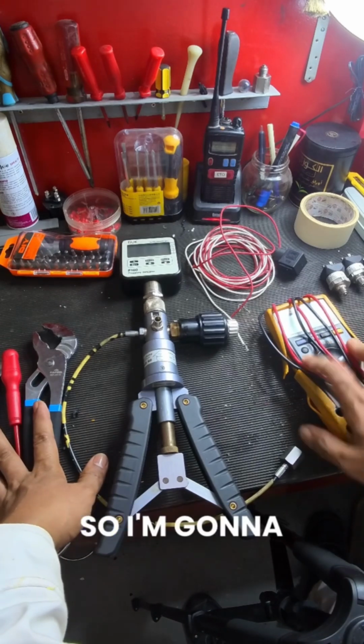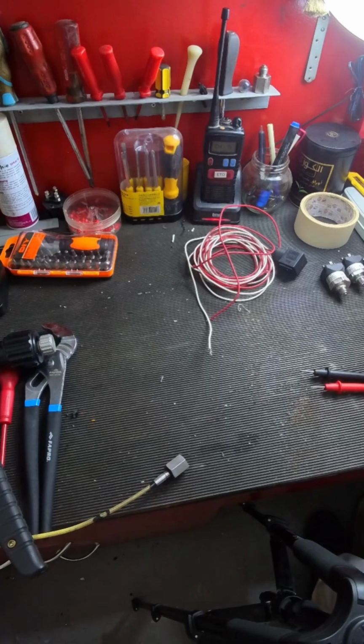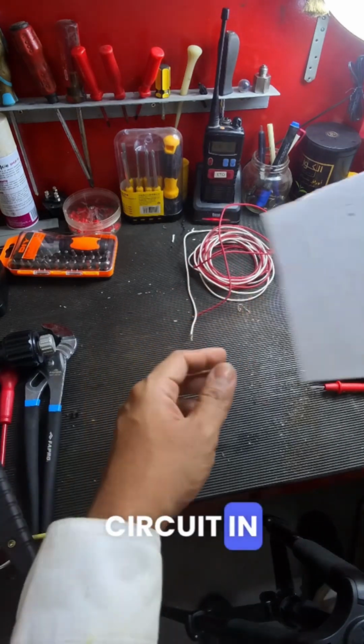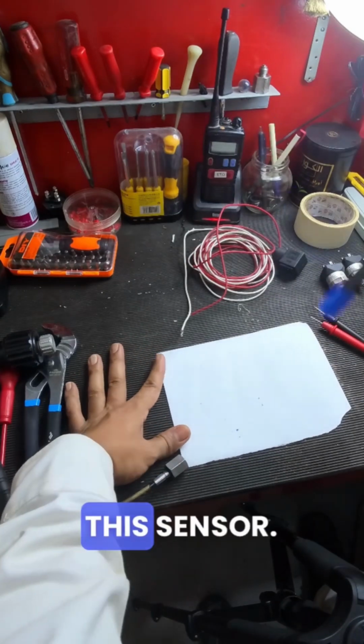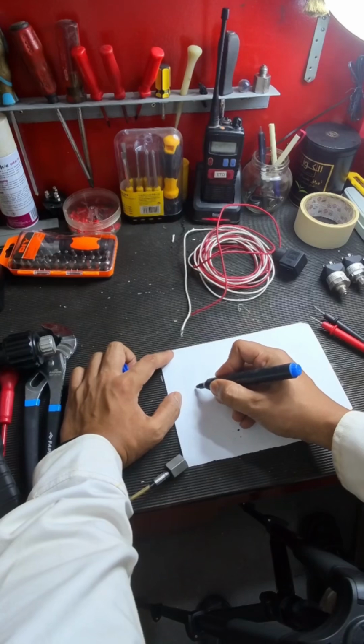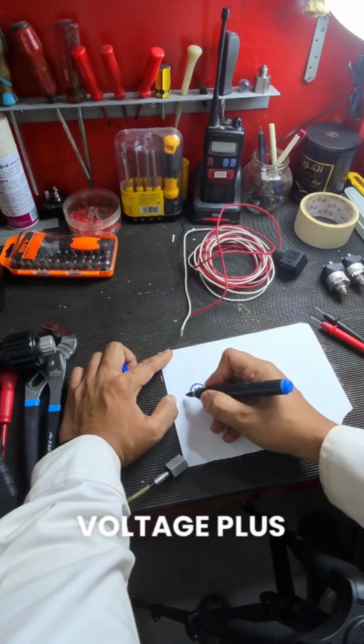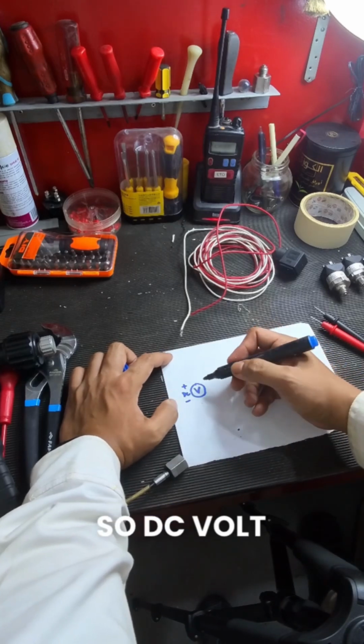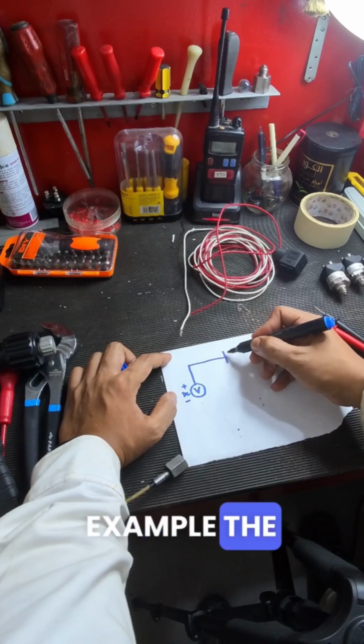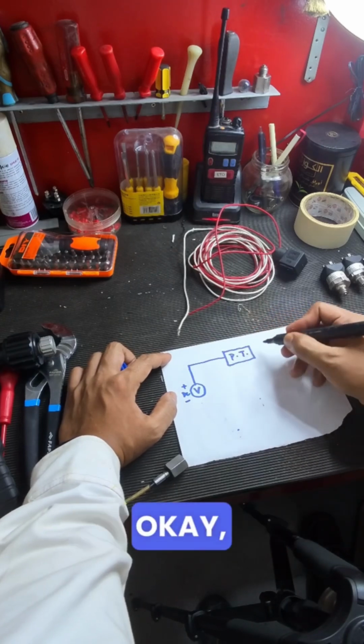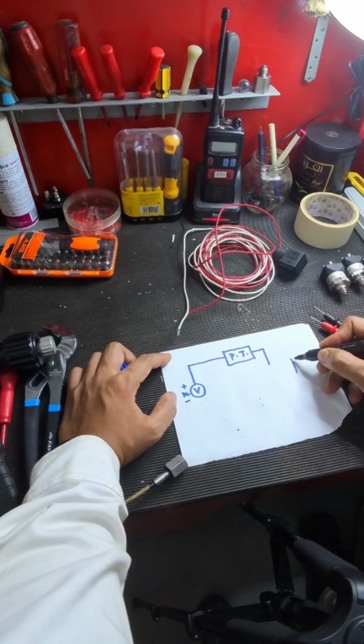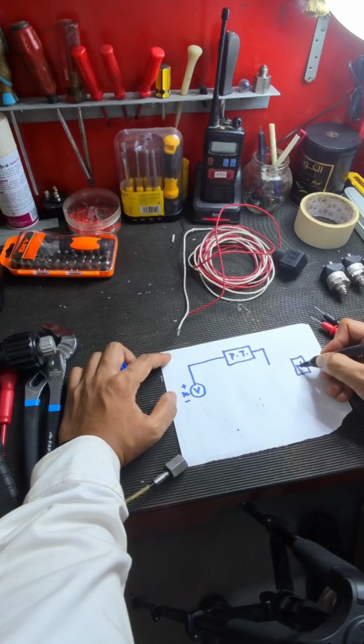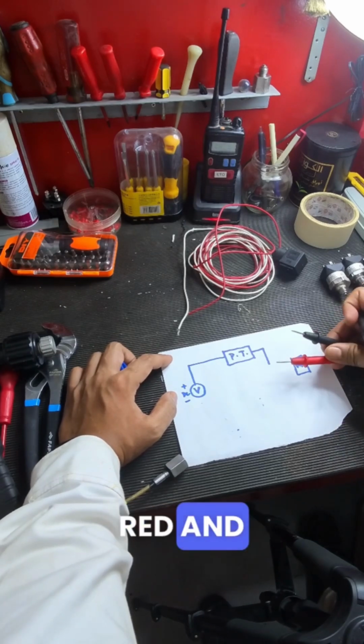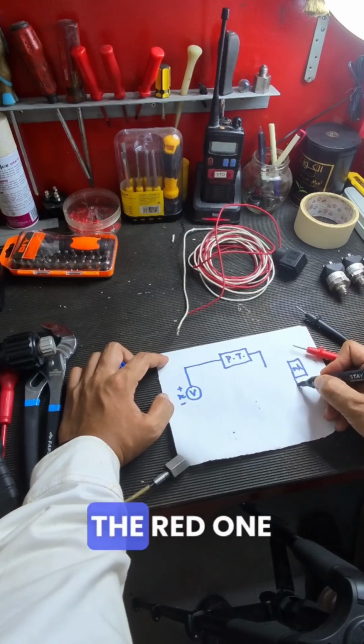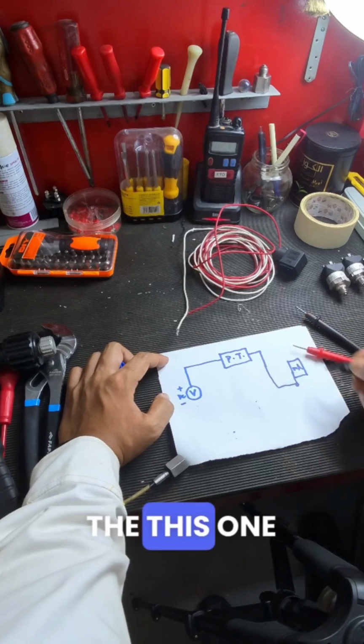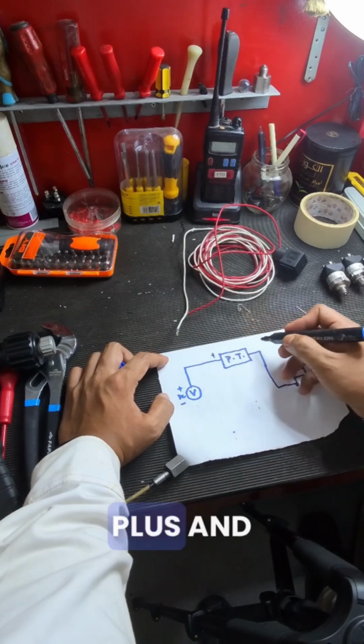I'm going to show you how to connect the sensor, or how to make a circuit in order to test these sensors. We have a power supply source, for example this one, with voltage plus and minus, DC volts. Then it goes to the sensor, which is the pressure transmitter. We also have to connect the multimeter, set to milliamps. There are two probes, red and black. The red one you must connect to the positive, and this is the negative.